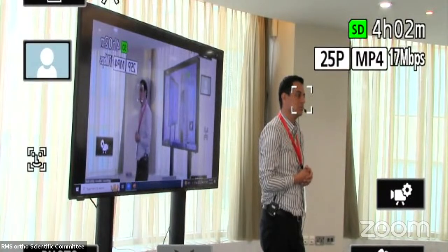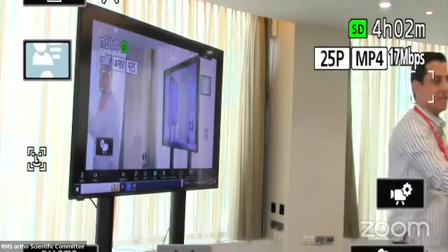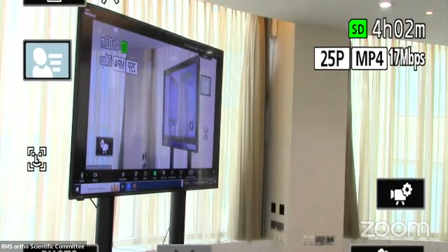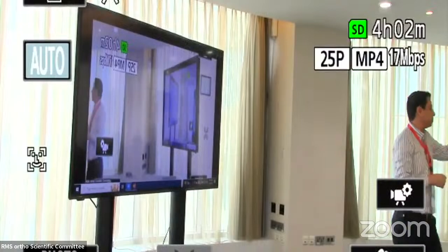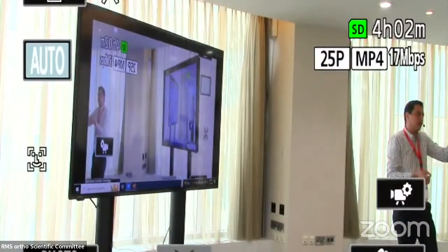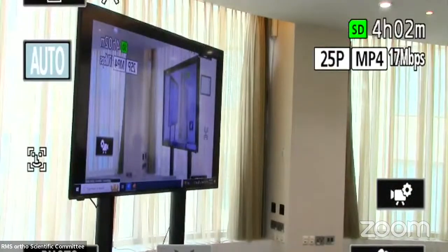Making it more accurate, easier, user friendly. So I think we use the coin, as Razi said. I don't know what you used for calibration before. Maybe the strut or the rod, 6 millimeters, which is fixed. I don't know what tricks we can use to make the calibration.